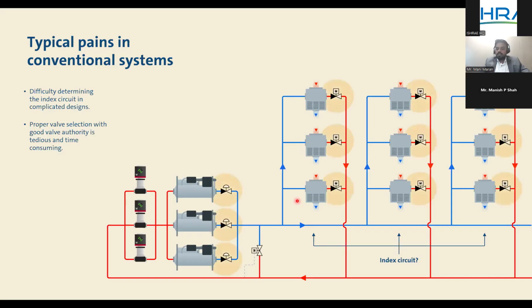Proper valve selection, as I said: ASHRAE 90.1 clearly defines that valve authority is something critical in design consideration. We see that it is compromised in most situations. If we compromise valve authority, then the balancing will be poor. That will impact the delta T of the system. And design performance completely relies on how we balance the system, how we maintain the balancing of the system throughout the operation over many years. If that is compromised, it will pull down the efficiency of the pump, and it will pull down the efficiency of the chiller.